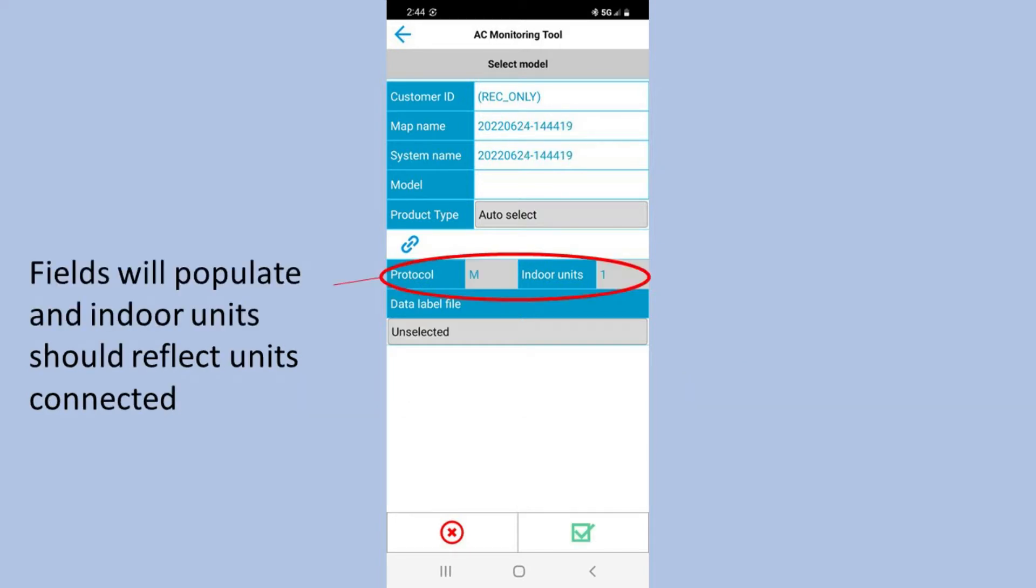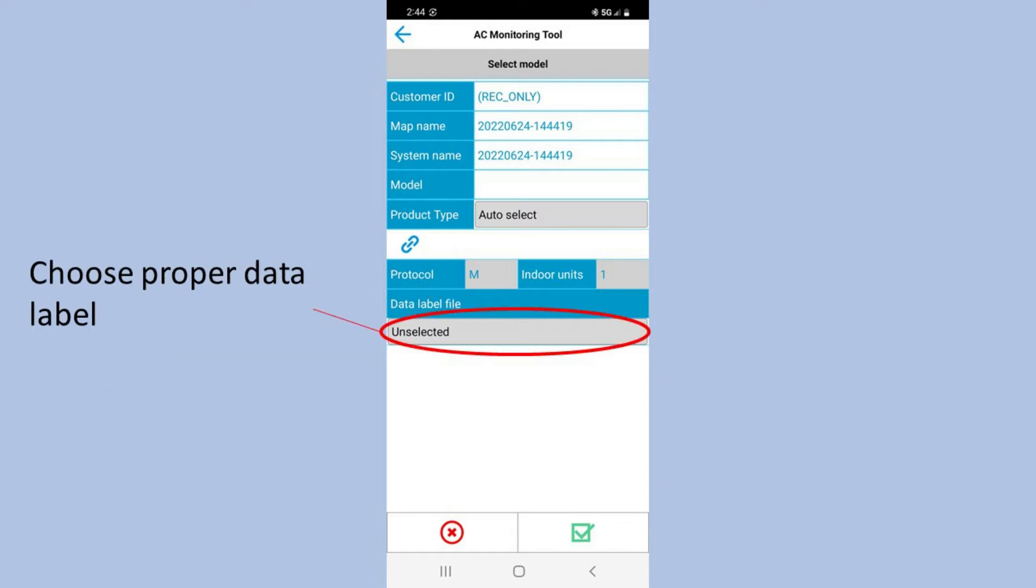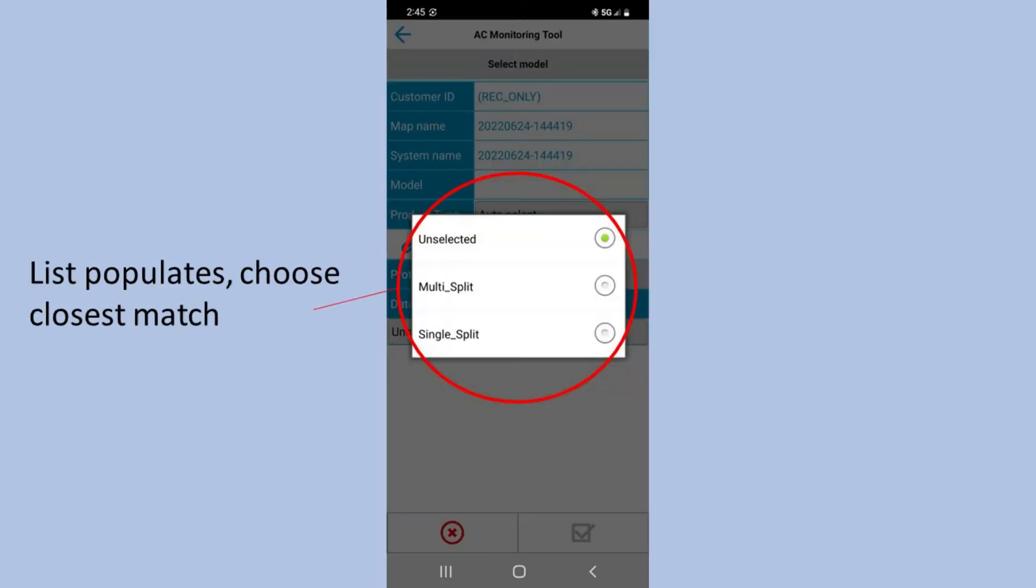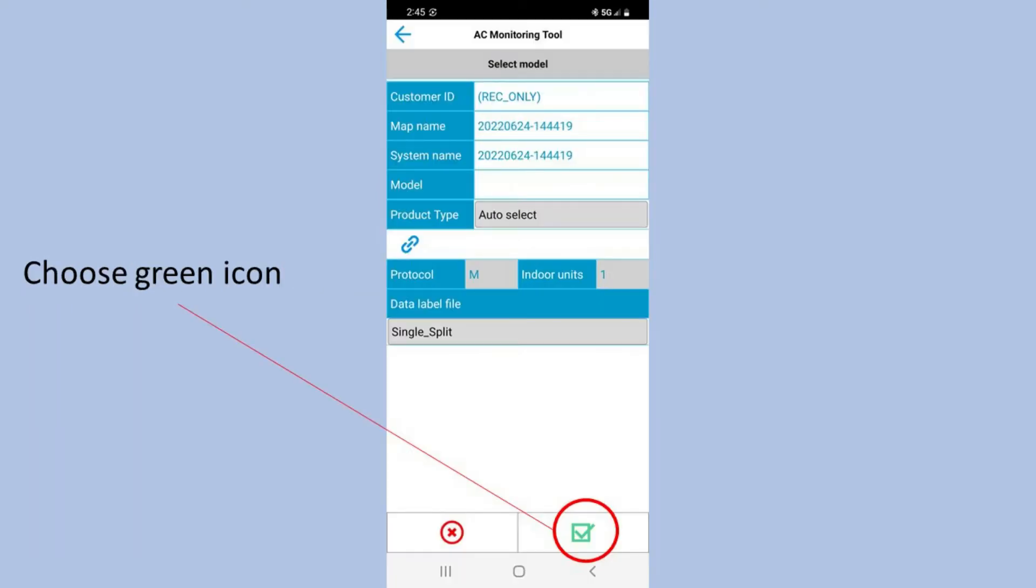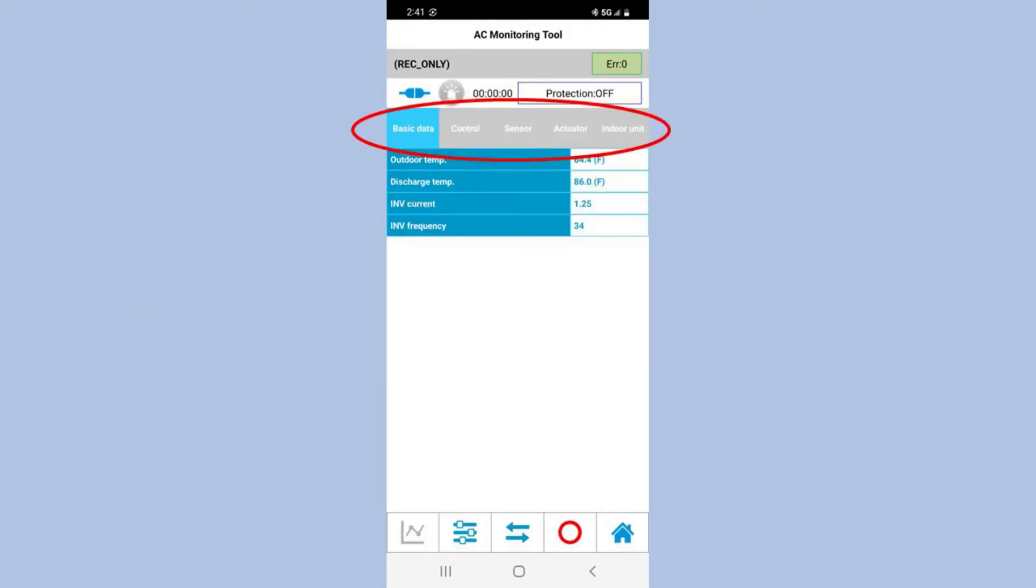When you do connect, this is what you're gonna see on the screen. You'll see your protocol, you'll see indoor units. In this case there's one, and I'm gonna go to the proper data label, and that's so it knows which sensor is doing what. In this case we're gonna choose the unselected and we're just gonna see two items, a mini or a multi. And if you're doing different models, you want to carefully look at your list and make sure you get the unit closest to the one you're working on so those data labels are correct. Otherwise it may put the suction pressure with the head pressure and temperature, etc.